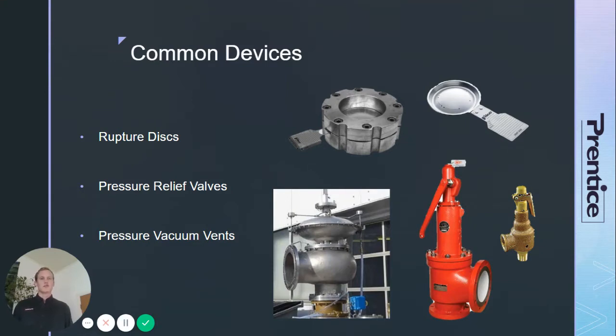Rupture discs are a non-reclosing device — once they're open, you have to replace them. Relief valves are what you're going to see at the top of a boiler, and pressure vacuum vents are used most often on storage tanks when the set pressure is below 15 pounds gauge. We'll talk about why the line is drawn at 15 pounds.